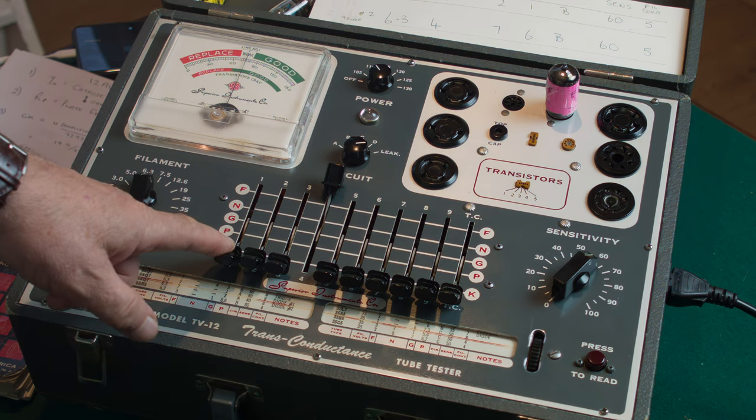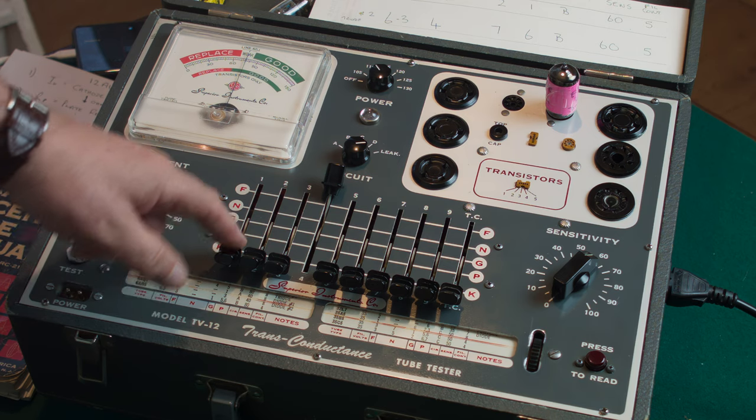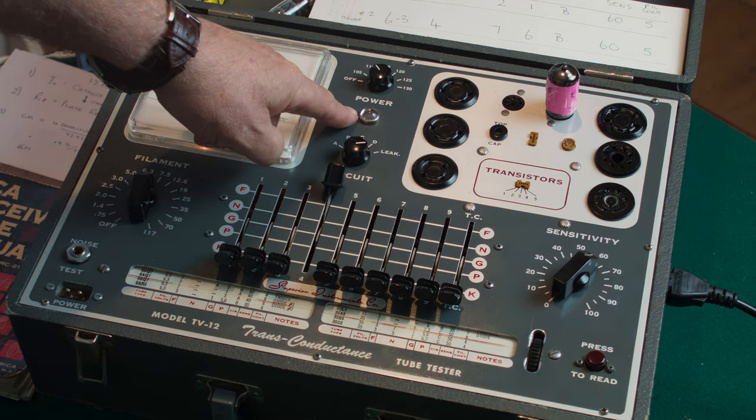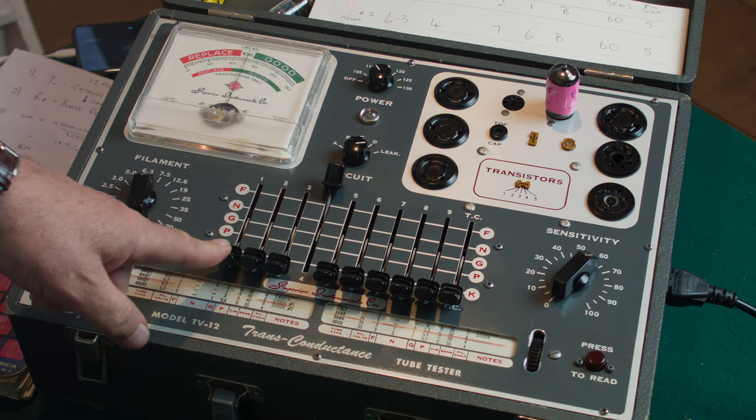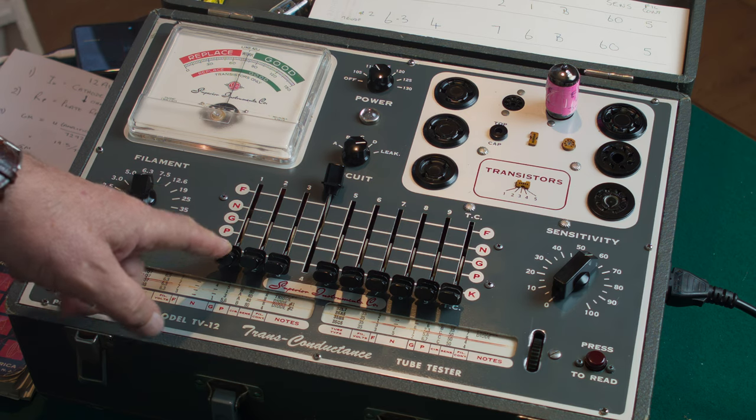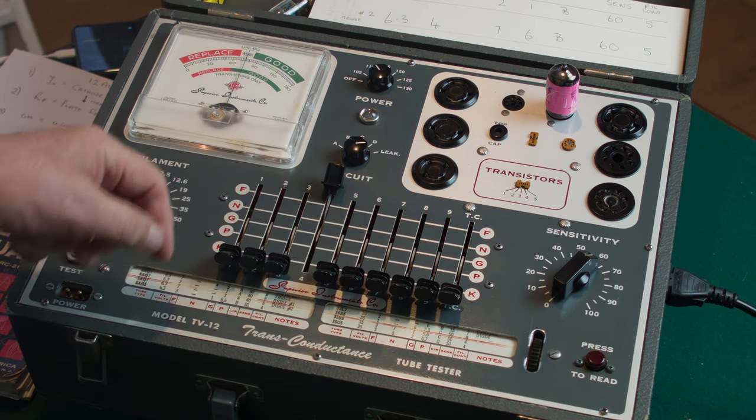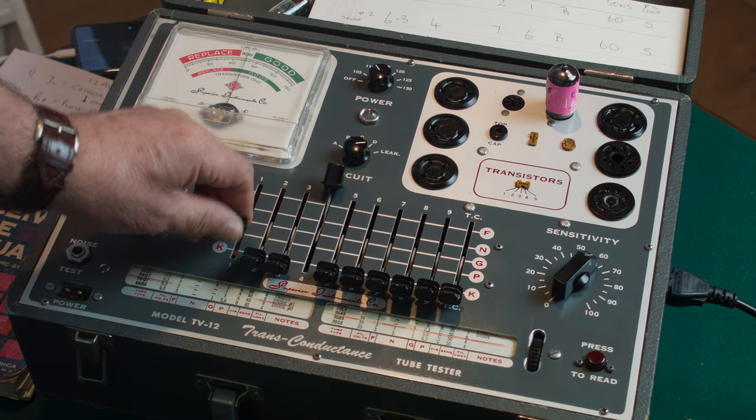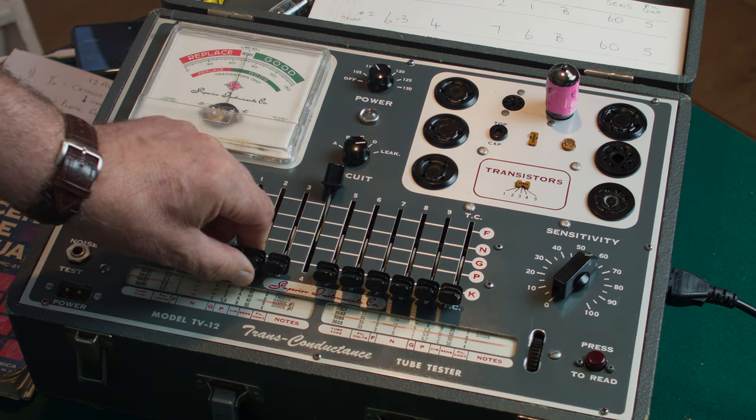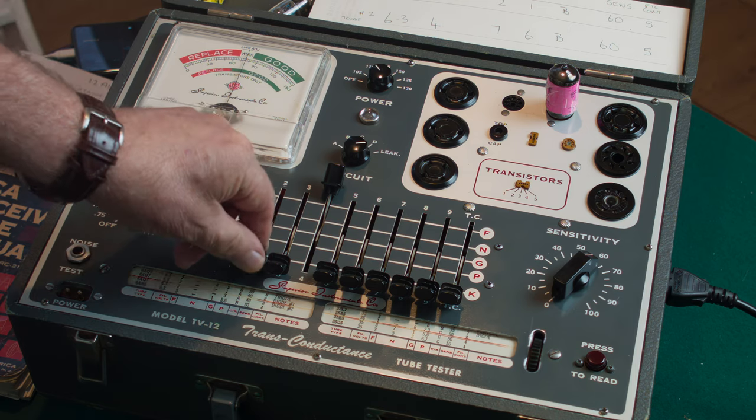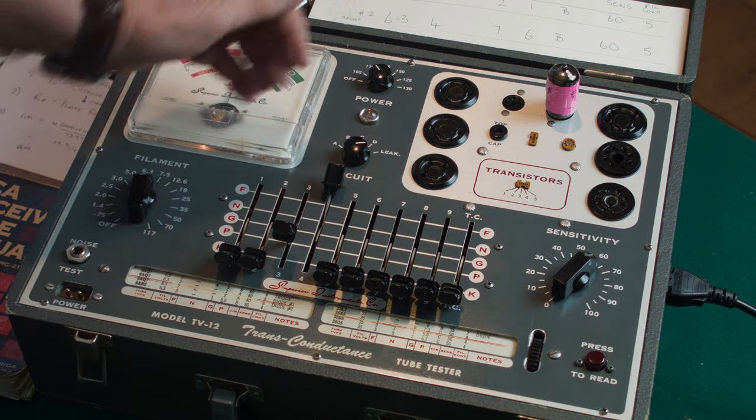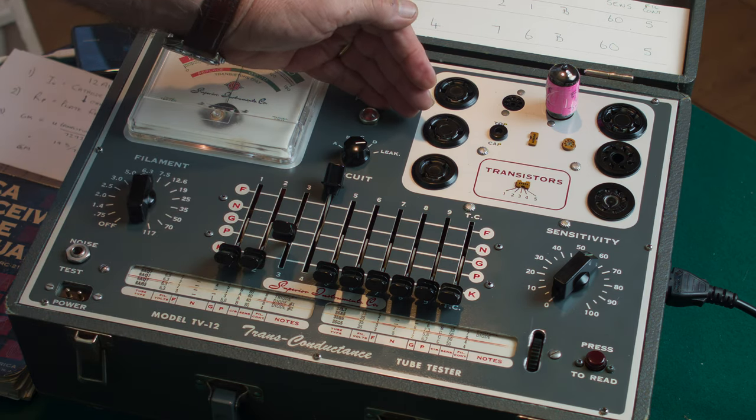All we're going to do is move these levers up one at a time to the P position and down again while watching this neon lamp here. If it glows it'll be a short or leak, but there's another occasion when we move lever five up it will glow but that's only the filament. So number one first, that's clear. Number two. Number three.